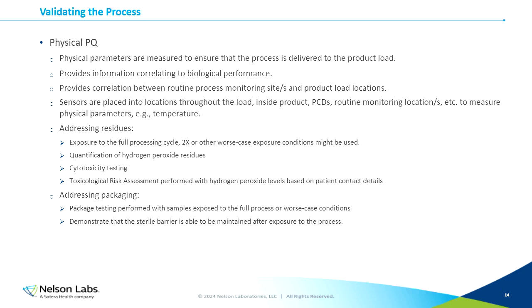And although we will get into addressing residues in detail in subsequent days of this series, I do want to mention the process very briefly. So to address residues, we'll expose the load to at least the full processing cycle. There may be times we decide that we want to expose it to 2 times the full processing cycle or other worst case exposure conditions. And that's something that might be made on a case-by-case basis. Once we perform the required exposure, we want to quantify the hydrogen peroxide residues coming off of that product. So we perform testing to get those numbers.